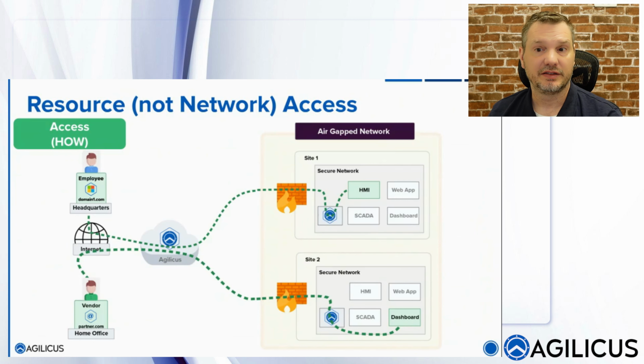All in all, this is what we want to provide in a public water system when we start having to enable vendor access, all through a zero trust model. We want to have outbound-only connections. Why? We don't want to have exceptions on our firewall. They're toil to maintain. They're hard to keep in sync. If we do a security assessment, for example, from a security posture, we can see ports listening. We don't want that. We want to have an outbound-only connection that is not listening to anything from within our OT network.